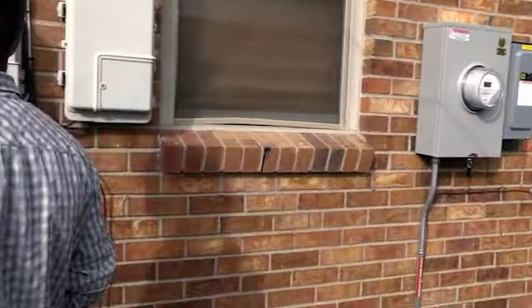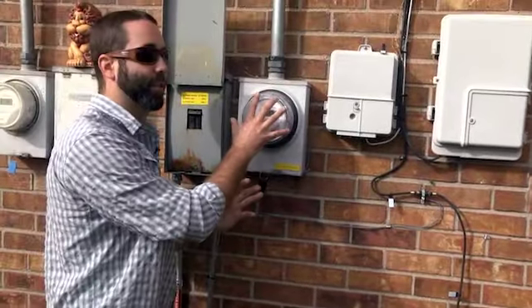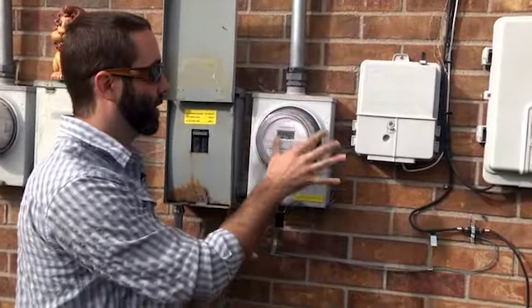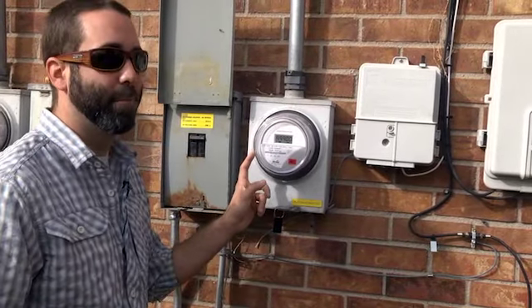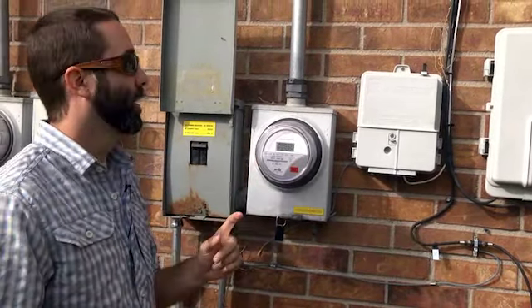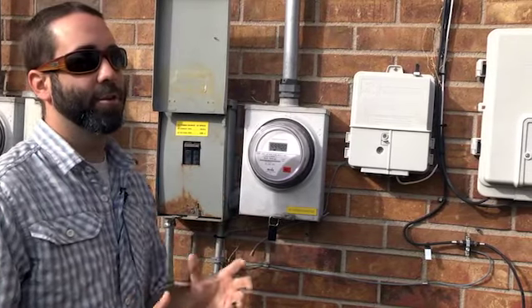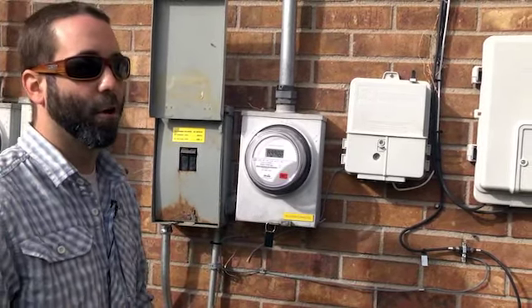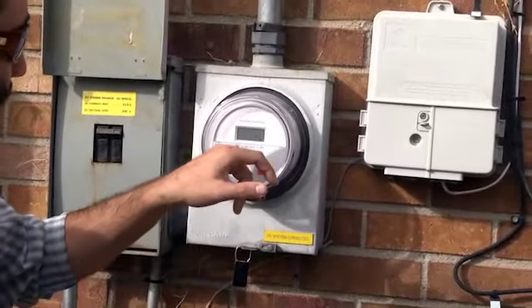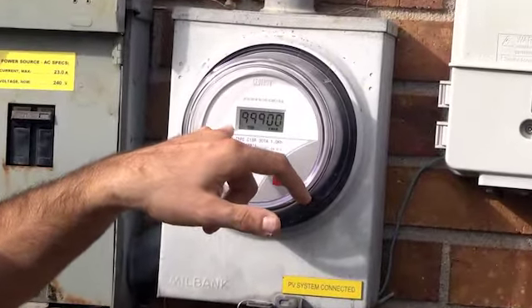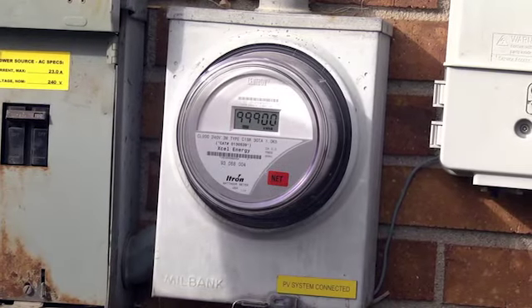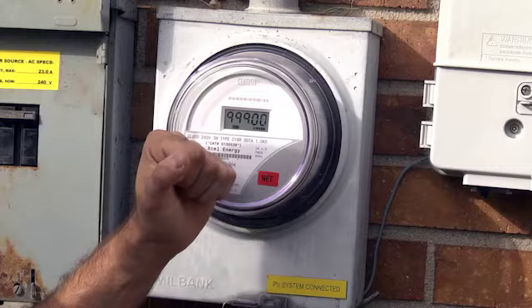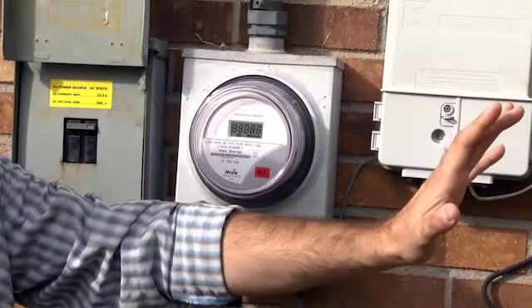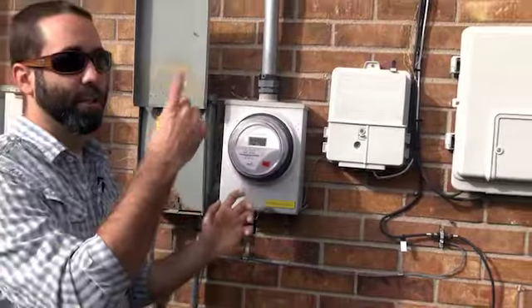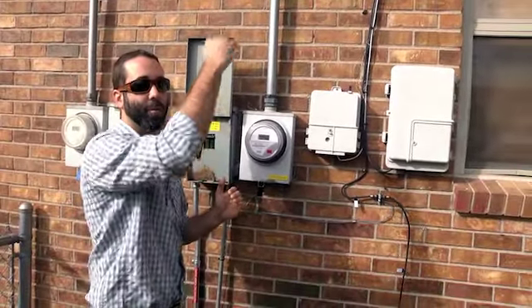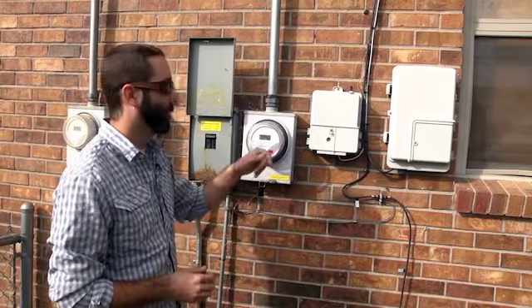Now, what Xcel has done is, previously there was a different meter in this housing. When we turned the system on, Xcel came out and installed what's called a net meter. The net meter has the ability to determine how much energy has been purchased from the grid over a given amount of time. Right now, this net meter is reading 99,900. The interesting thing about these meters is they start at 0 also. Let's say there was no solar being produced. Over time, you continually buy energy from Xcel. That number goes up and up and up. So if you bought 100 kilowatt hours in a month, it would read 100.